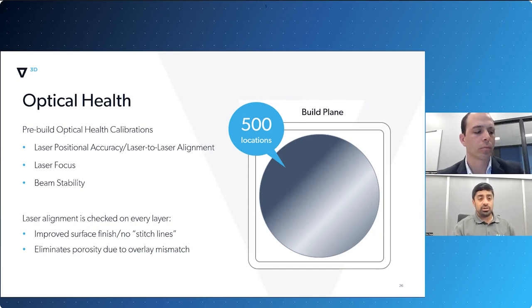On the optics side, during calibration we look for positional accuracy of the lasers, as well as laser-to-laser alignment. That's the reason you're not going to see a stitch line on a Velo part that's been printed with multiple lasers. We also check focus, as well as beam stability, and all of these things are automated.